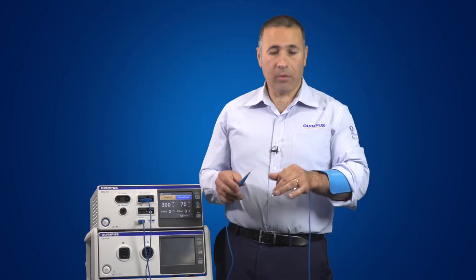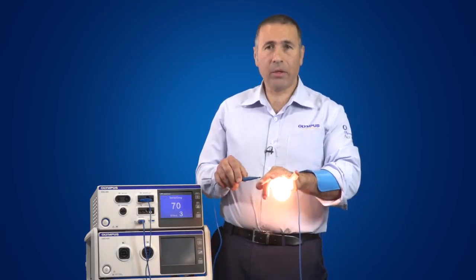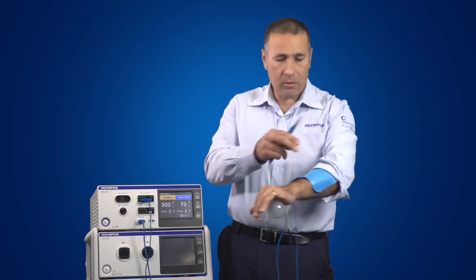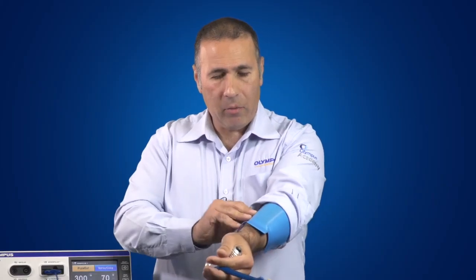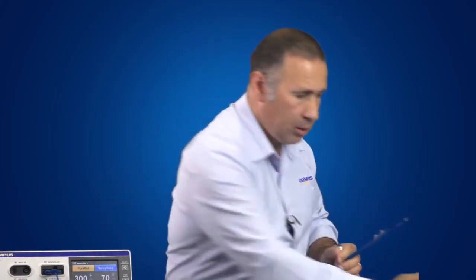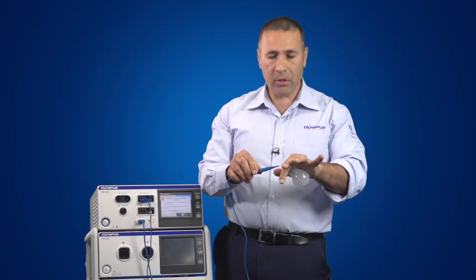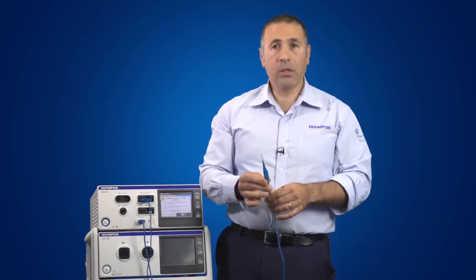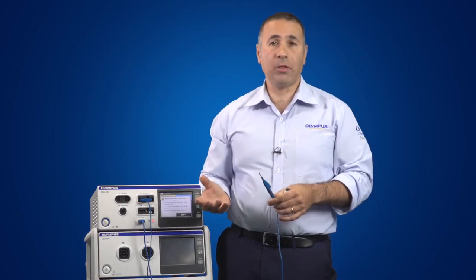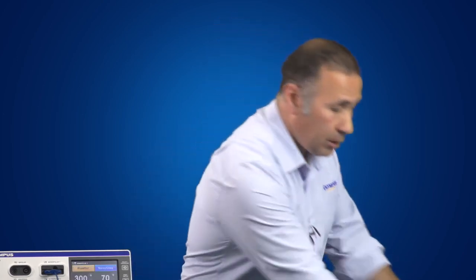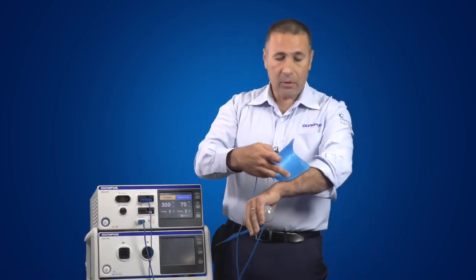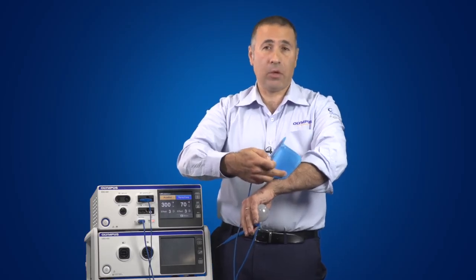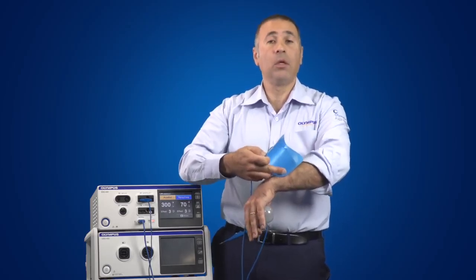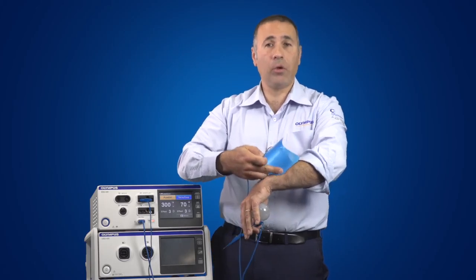So here I'm using an isolated generator in order to complete the circuit. Okay, so the patient return plate is returning the circuit back to the generator. However, if I remove the return electrode plate, there's no return in the circuit, there's no effect. So this has virtually eliminated all alternate site burns for patients, but you can imagine, as you saw with the current density demonstration, if the plate started peeling off where I had an area of high current concentration, then there's potential still for a patient return electrode site burn.